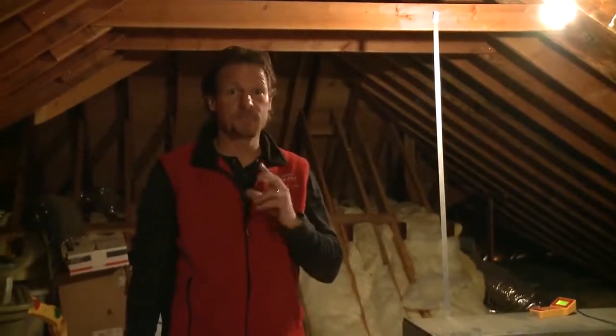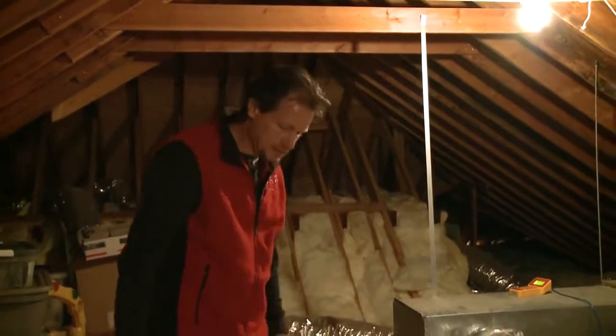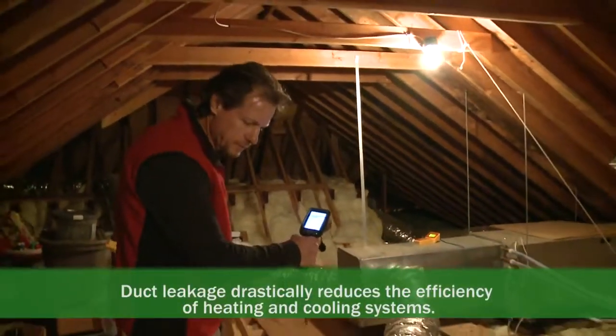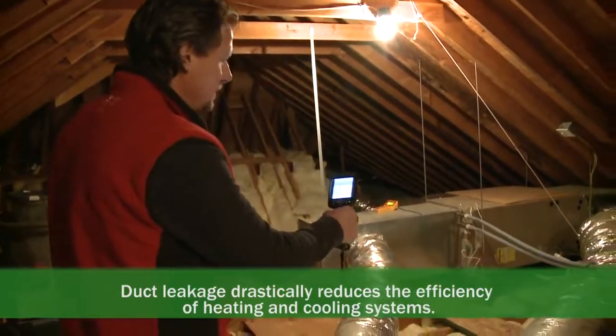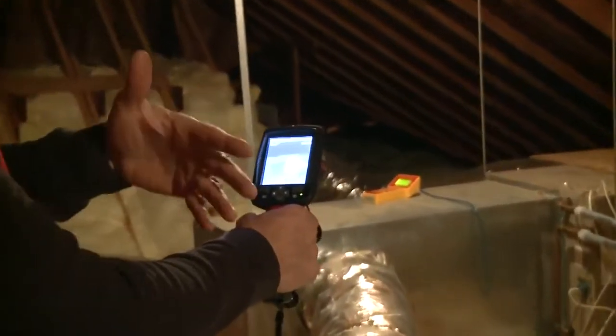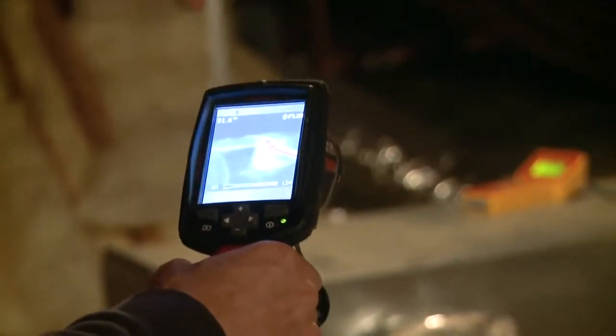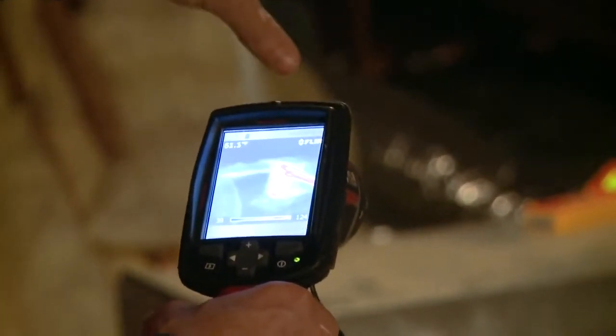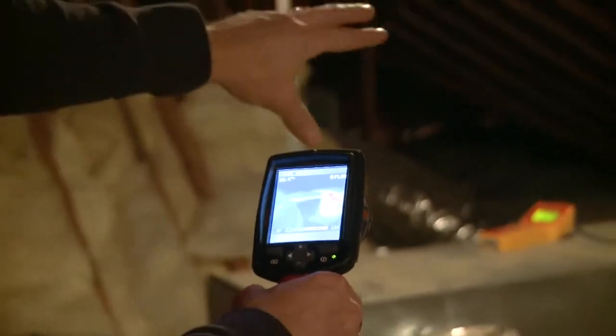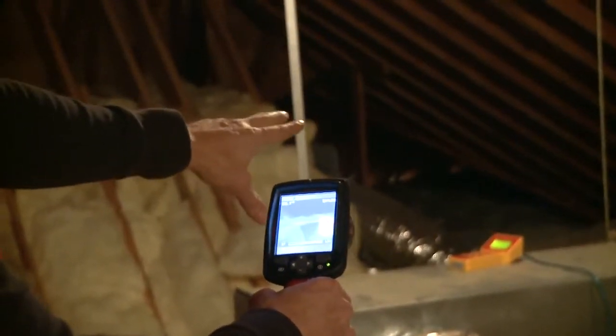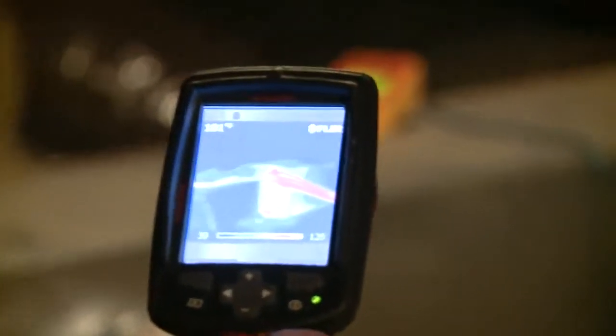All right, here we are in the attic, and there's one kind of leak that's more important than attic leaks, than A priority leaks, and we call them AA leaks, and that is leaks from ducts. And here we are, the air handler is running, and if we look at this duct system with a thermal imaging camera. Now this happens to be a hydro air system. There's a boiler in the basement running hot water to a radiator in that air handler. The air handler is a cabinet with a blower in it. And we're blowing the air over that radiator and getting heat out of it and running the heat through the ducts to the rooms. But look at, you can see the lack of insulation and the hot spots in this system.